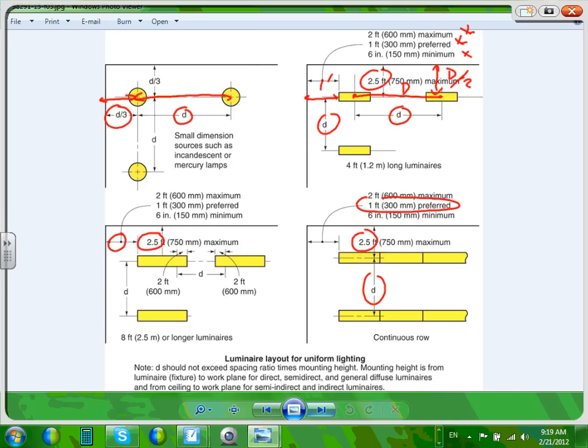Most of the time, Ashley, if you have a grid, 99% of the time, you don't want your fixture right against the wall unless there's a reason for that, like a board or something. So you move most of the time 2 feet because the grid goes 2 by 2. They don't go half, 1 by 1. So there's your 2 from this side, and from the other side is also 2. So 2 by 2, and you start gridding your fixture. You go from that corner 2 by 2, 2 by 2, and you start your grid, gridding your fixtures.